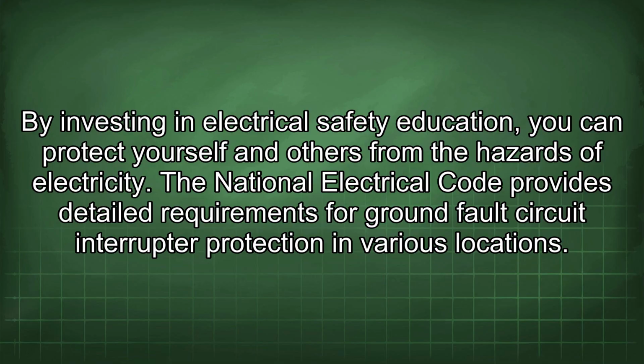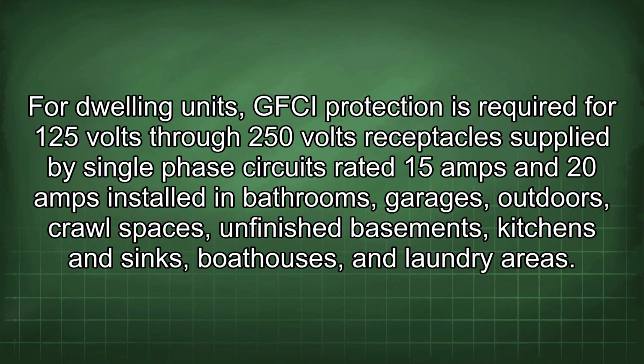The National Electrical Code provides detailed requirements for ground fault circuit interrupter protection in various locations. For dwelling units, GFCI protection is required for 125 volts through 250 volts receptacles supplied by single-phase circuits rated 15 amps and 20 amps installed in bathrooms, garages, outdoors, crawl spaces, unfinished basements, kitchens and sinks, boathouses, and laundry areas.